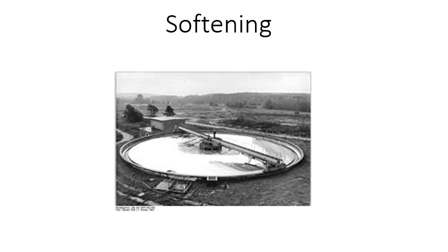So to remove non-carbonate hardness, permanent hardness, the magnesium chloride, magnesium sulfate, calcium chloride, notice that none of those have carbonate in them. You're going to dose with excess lime, so about a 15% overdose. So magnesium hydroxide will settle with excess lime addition. The pH is now above 11.3.